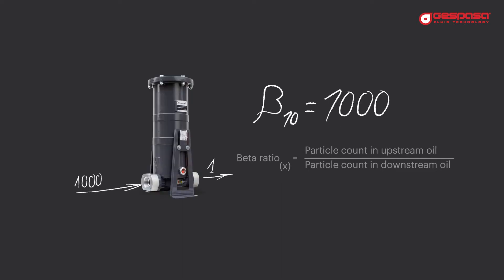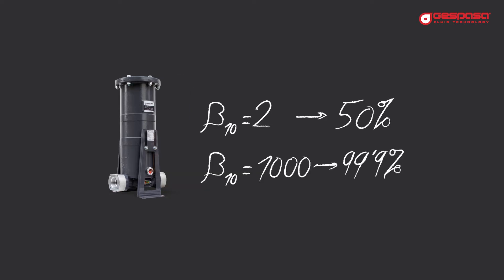A beta 1000 filter at 10 microns will allow only one particle out of every thousand to pass larger than 10 microns. We can indicate the efficiency of the filter in beta factor or in percentage. Beta 2 equals 50%, beta 1000 equals 99.9%.